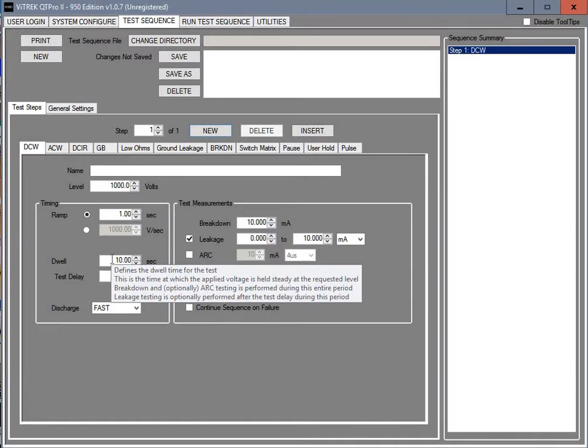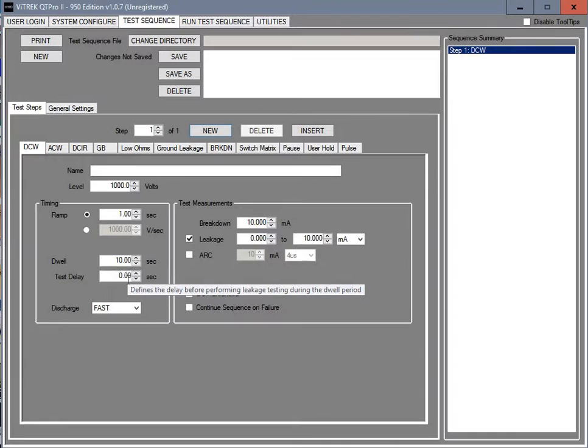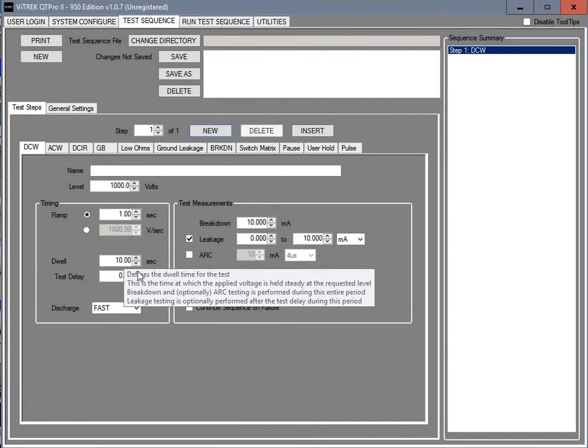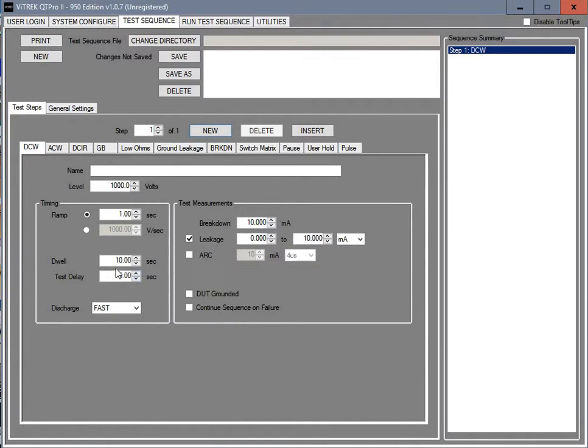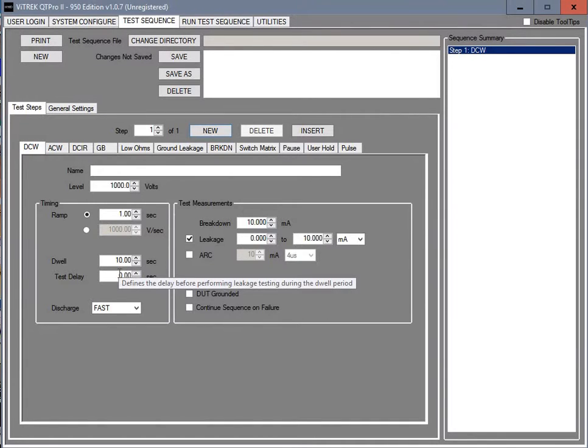Your dwell is how long it's going to stay at that particular voltage once it gets there. And your test delay, what that does is it delays the enforcement of the test for a second or two, depending on what you give it, time to settle.